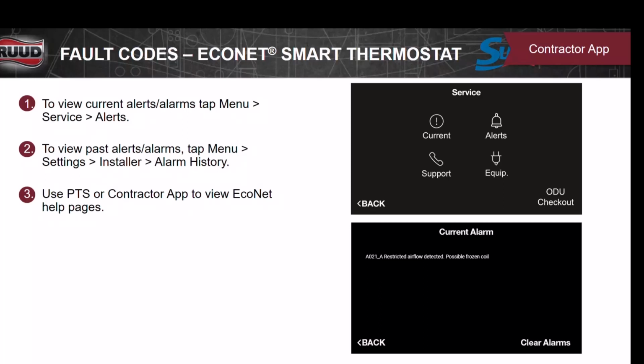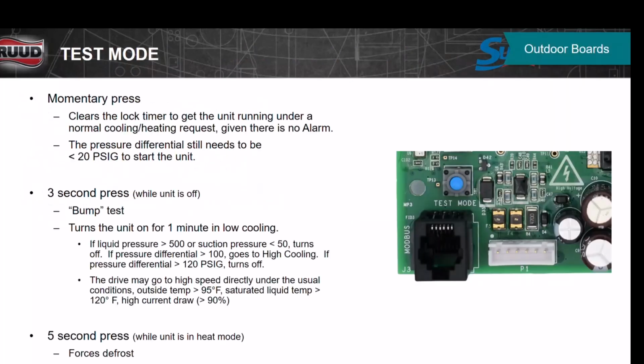And then you go to your alert and take a picture of that screen. Call me then. Now I know what equipment's in there, I know what revision the boards are, and I know what the error code is. It makes it easier and faster for me to help. The lockout timer, this clears the lockout timer. You can do it manually on the thermostat or on the app.